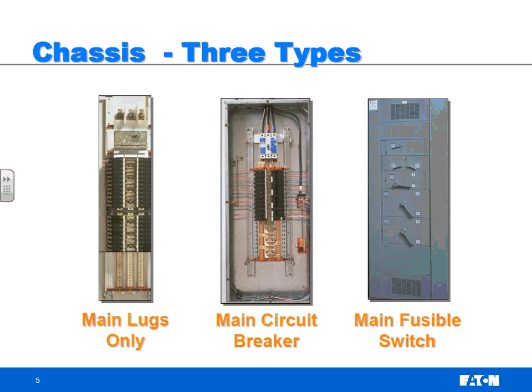When I talk main circuit breaker or main fusible switch, it's really the same concept, except you're using fuses instead of circuit breakers. What's the better method to use, circuit breakers or fuses? Circuit breakers. Why? Well, we don't make fuses, so. But fuses are the way they used to do it in the old school. A lot of people still use fuses today, and you'll never get them to change. But circuit breakers have a much greater advantage, or a longer list of advantages than what a fuse could offer.